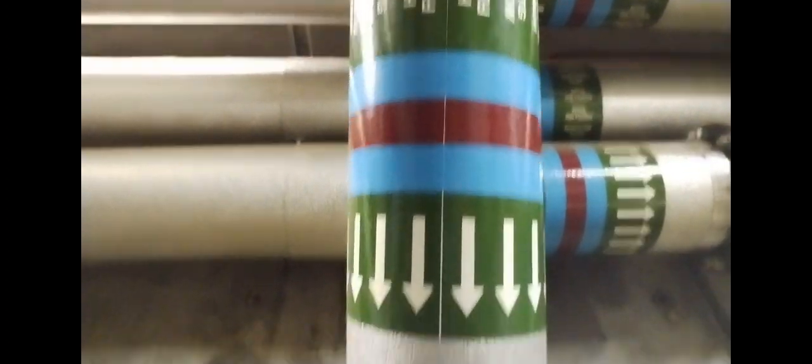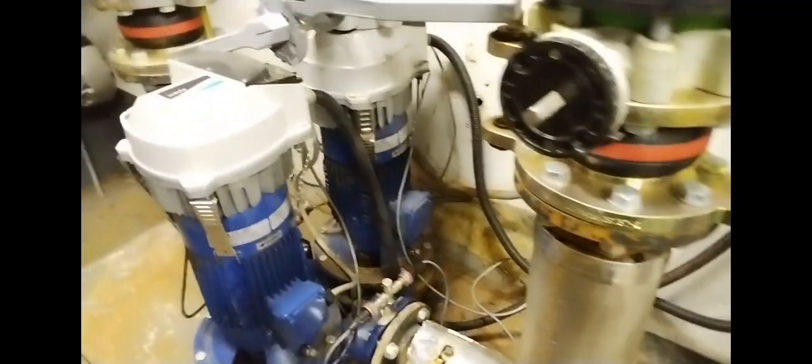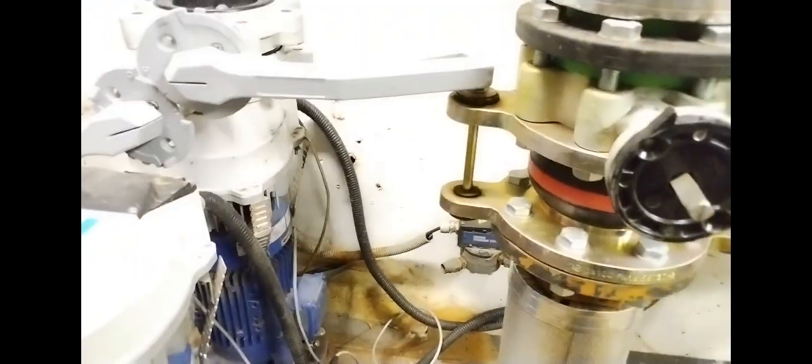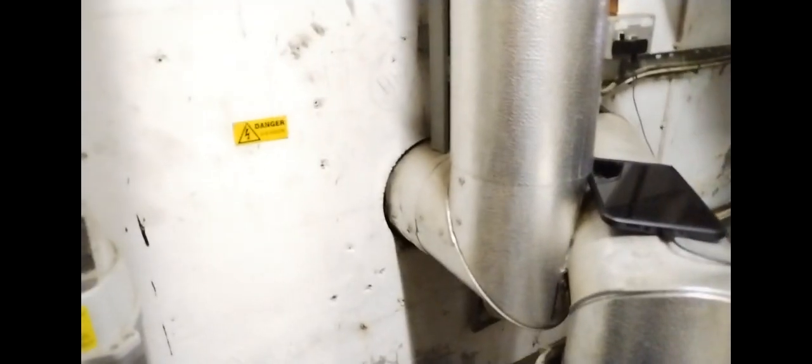Hi, welcome to the Commercial Gas Engineer channel. Just in this plant room checking a few things out, tracing the pipework, the constant temperature and variable temperature circuits. It's often that the labeling on pipework is not correct, so don't see it as gospel. If you see the arrows pointing a certain direction, don't take it for granted that is the flow. Sometimes the people that did lagging don't know what is what.